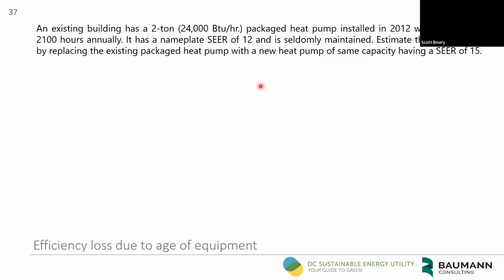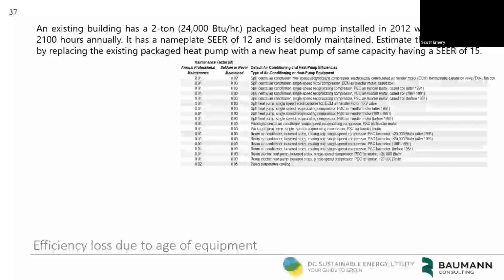So, an existing building, here's an example. An existing building has a 2-ton packaged heat pump installed in 2012, which operates 2,100 hours annually. Its nameplate SEER is 12. It is seldom maintained. The estimated energy savings come from replacing the existing packaged heat pump with a new heat pump with a SEER of 15.